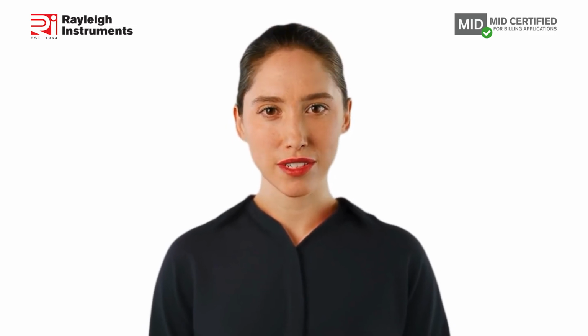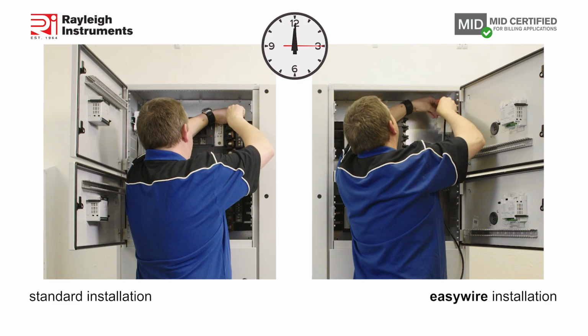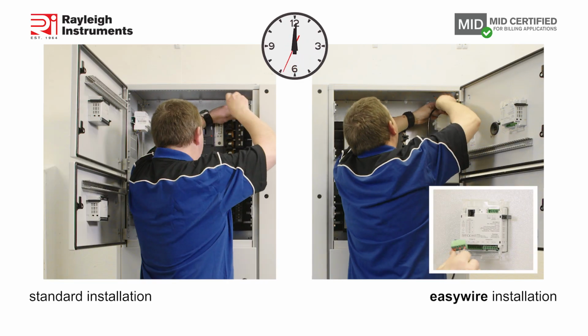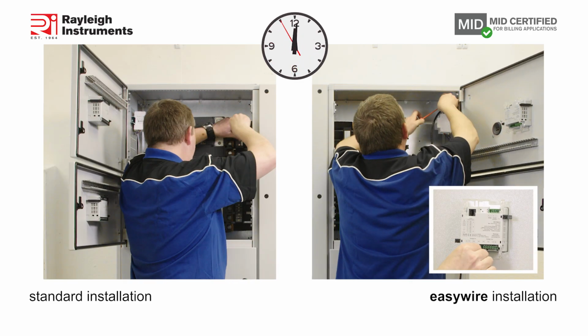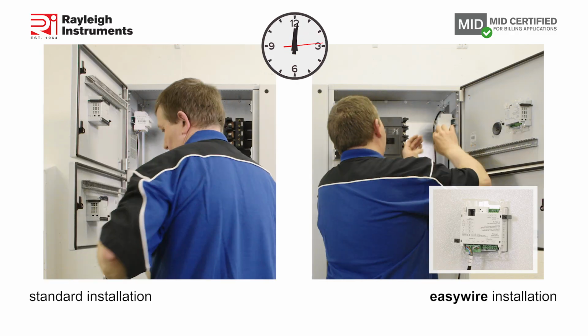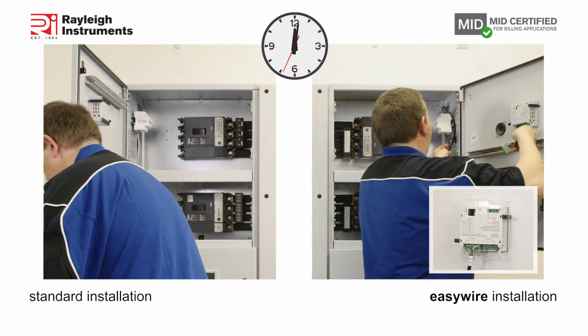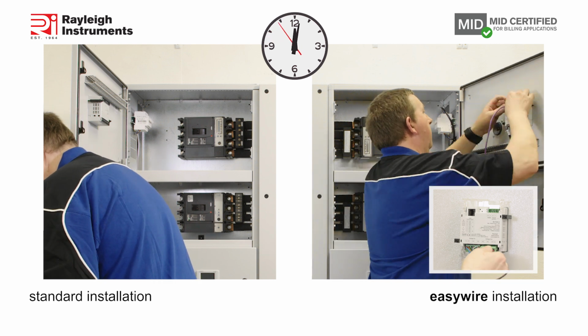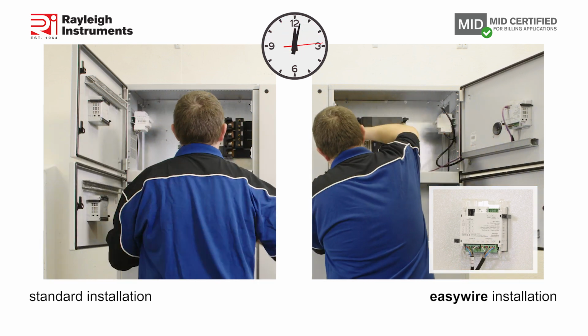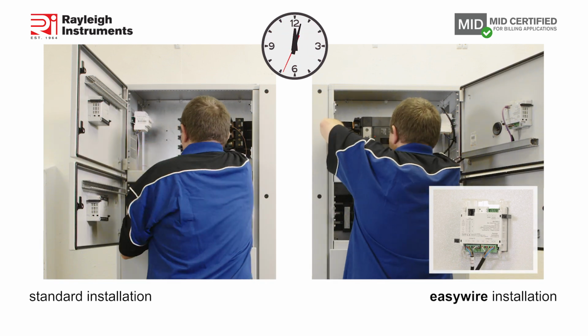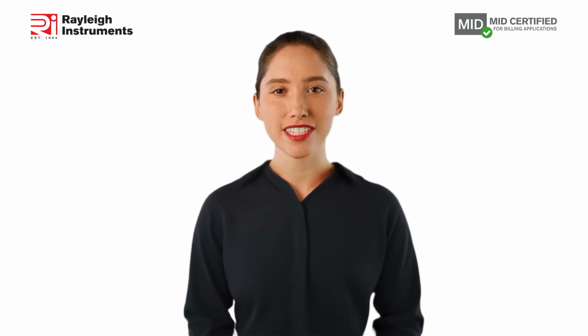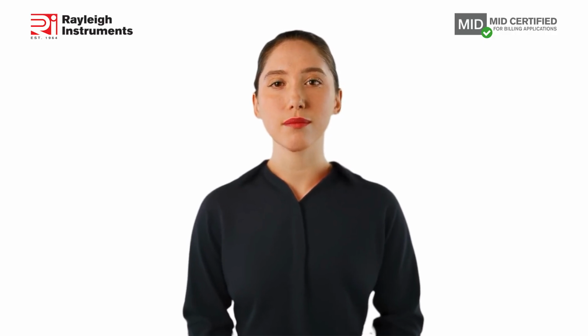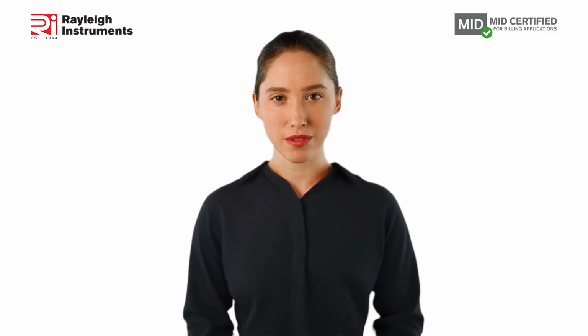plug-in wiring looms. With Easywire, you connect the pre-made meter voltage supply cable from the fused main supply to the power-in plug on the first meter. Next, plug in the pre-made meter-to-meter supply cable into the power-out plug of your first meter. Easywire meters are designed to daisy-chain power from meter to meter for up to 32 energy meters in a row.